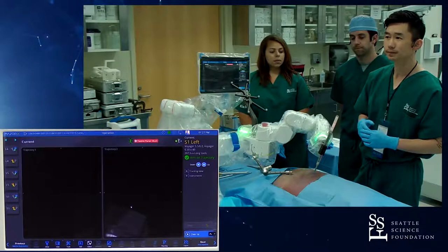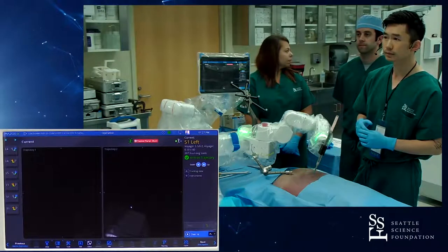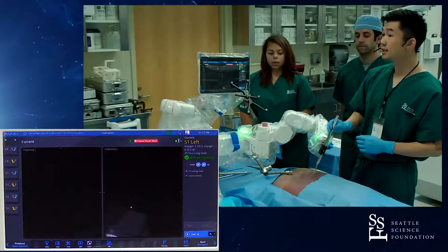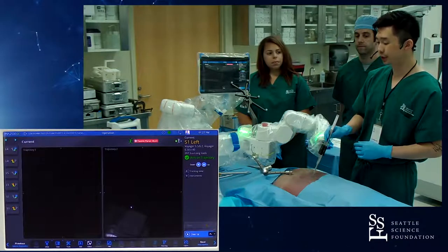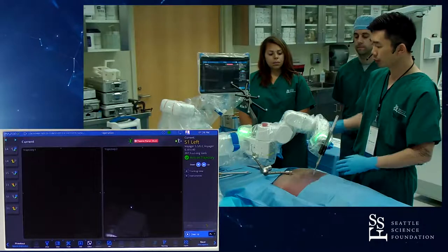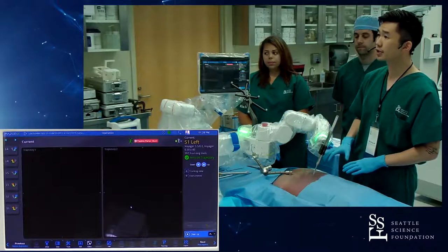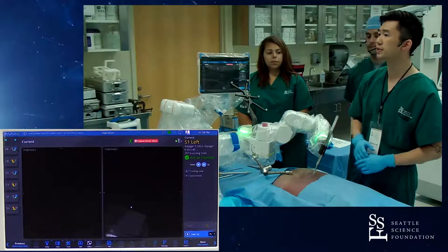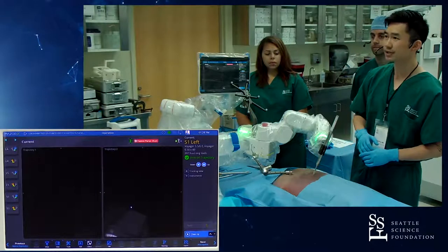Is this related to the surface scan that the platform performs? The surface scan you saw earlier is purely from a safety standpoint, so that the robotic arm doesn't collide with the patient and that it can maximize its movements and efficiency.